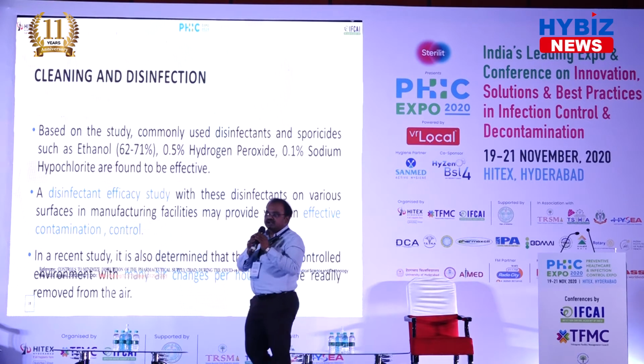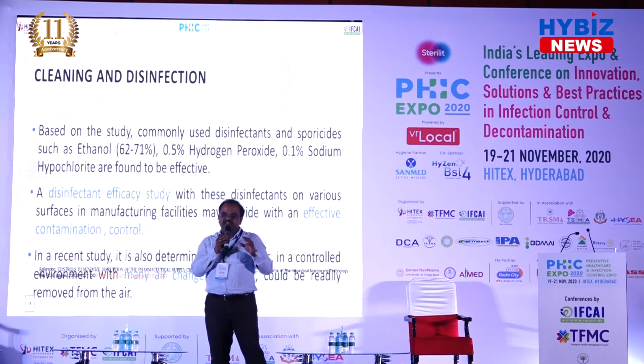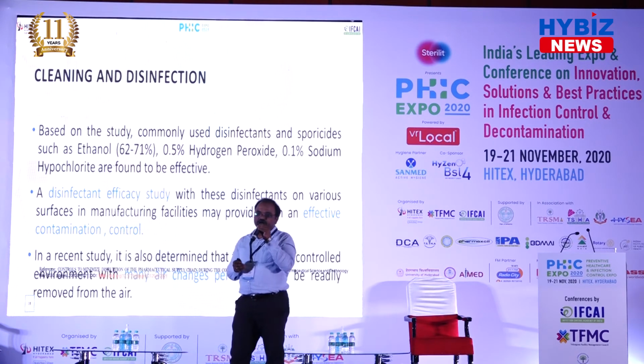Now, there are several criteria. For example, if a person is infected, what do we do? We use 2% bacilloid. We do fumigation across the area. That is the highest concentration, 2%. Followed by equipment cleaning, followed by floor cleaning. Floor cleaning will use 0.5% and equipment cleaning will use 1%. Most of the equipment will be cleaned with 70% IPA, isopropyl alcohol. This is the strategy, and we have to have documented evidence to support these activities.